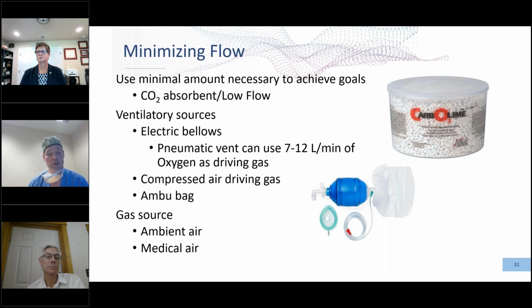So the anesthesia machines actually have CO2 absorbent. The same concept is used in rebreathing scuba diving. Basically, you can go very low flow. You just take out the CO2, you can rebreathe the oxygen and the other gases, but you have to have ventilators that are capable of doing that.